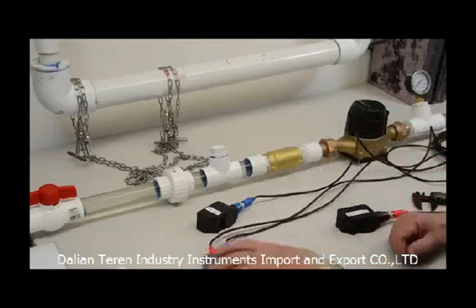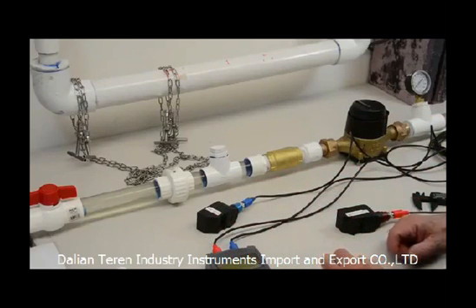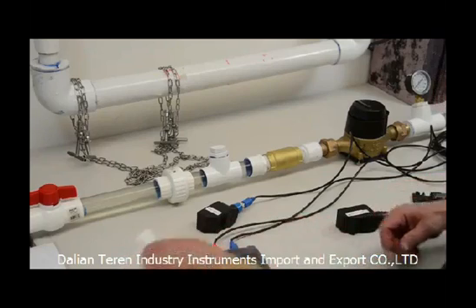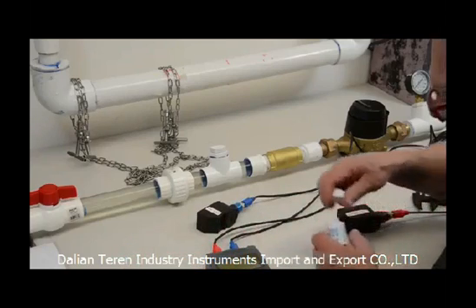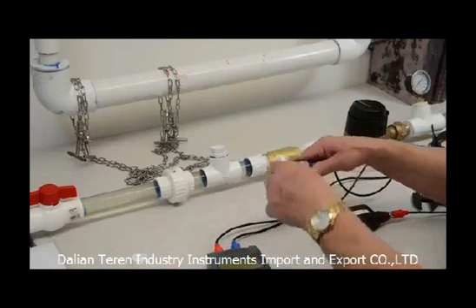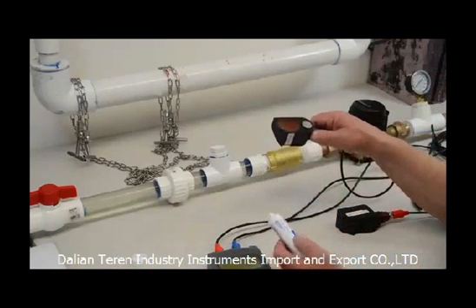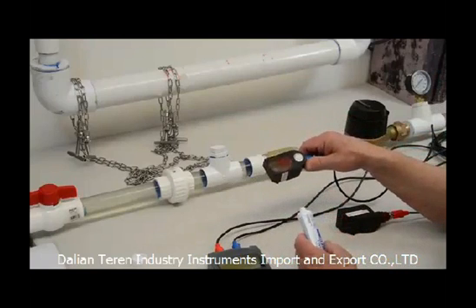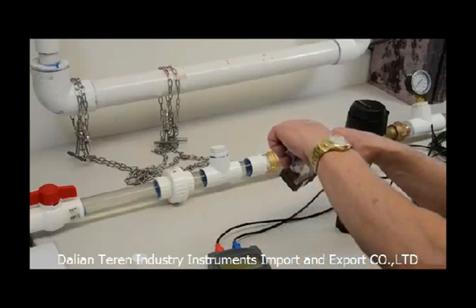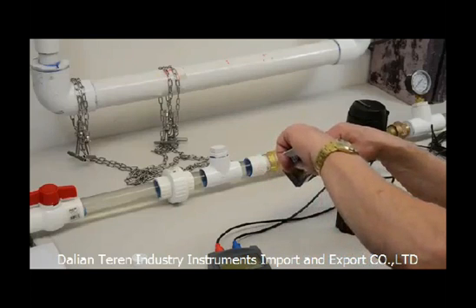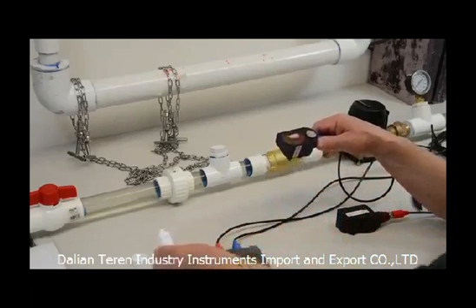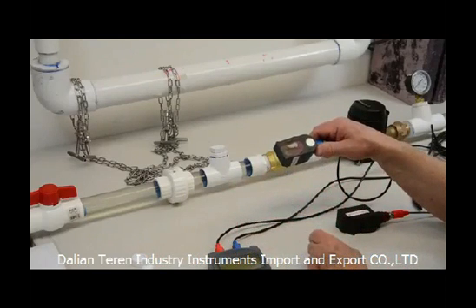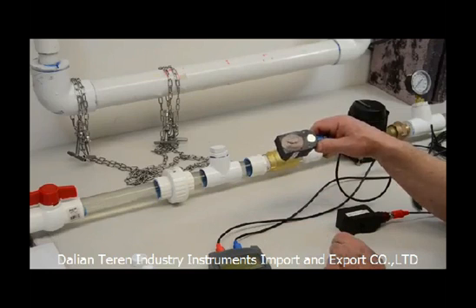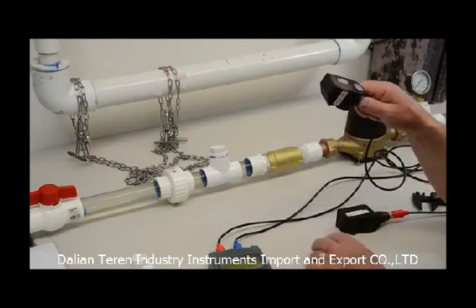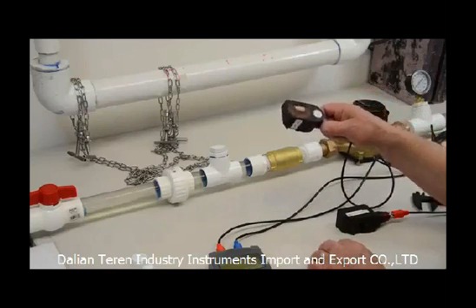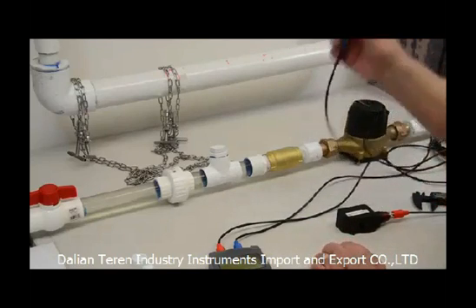Okay, so I've got my transducers attached to the cables, and before I install the transducer, my next step is to put a dollop of petroleum jelly on the sensor side of the transducer, and in this case I'm using Vaseline. Do not use a water-based jelly. It's absolutely imperative you use a petroleum jelly. Okay, so now I've got my spacing. I know I'm using 0.91 inches, and so I'm going to install the transducers.